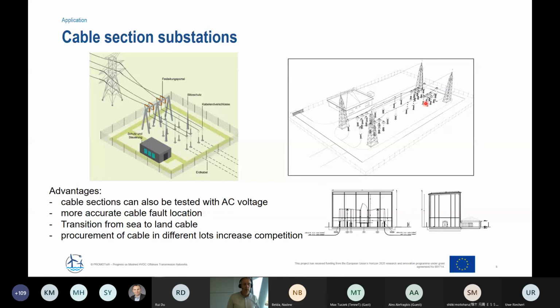This means the cable sections, not the substations themselves, could be tested with AC voltage, since the length is not so long and the power needed for testing is not so high. That's the first approach.